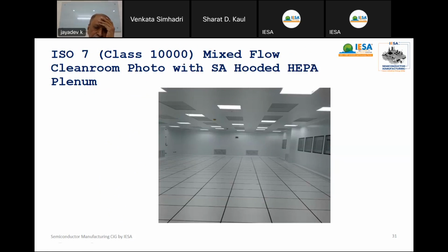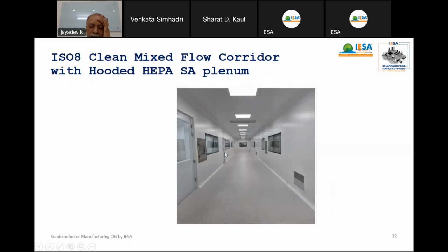And as a result, this mixed flow may be more suitable for OSAT assembly packaging. ISO 7 clean room with a mixed flow, you can see the hooded HEPA in the ceiling, light fixtures, and return air possibly all along the wall. And you can see the clean corridor itself, how clean it looks. ISO 8 is class 1 lakh corridor. This is a picture taken from a facility we recently built.